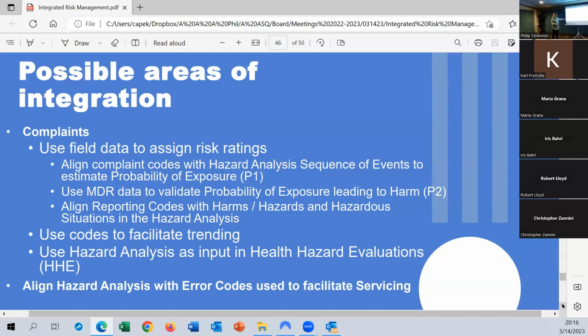I've actually helped people take their devices and design their error codes. Like, you have a sophisticated device that comes up with error code E02. Well, you can map that code to your risk analysis and know, like, well, when I get E02, it means that this hazard could have occurred, or this hazard could occur. And then that helps you assess your complaints better, determine if you need a recall or whatever else you might need based on your risk file.